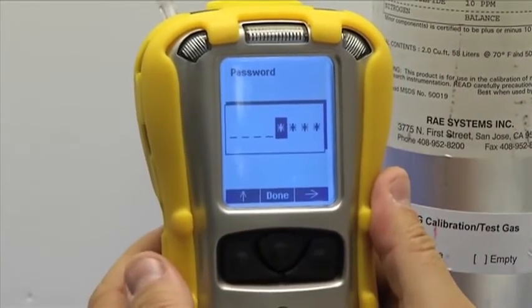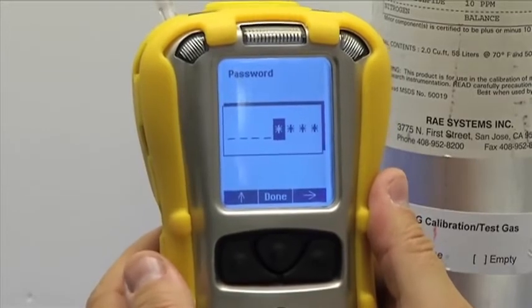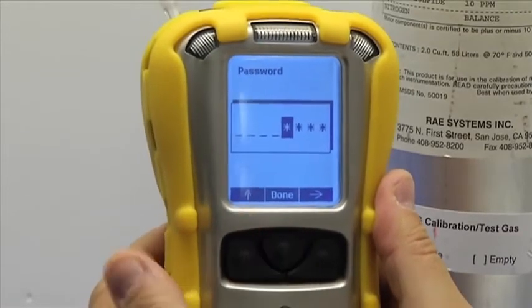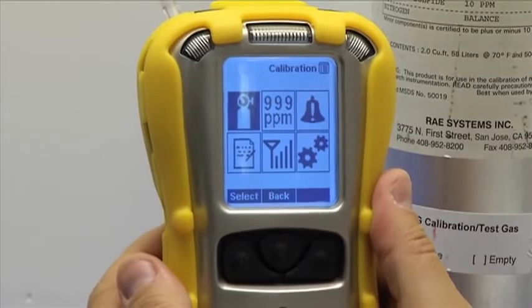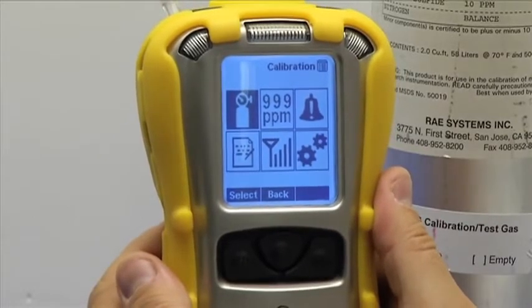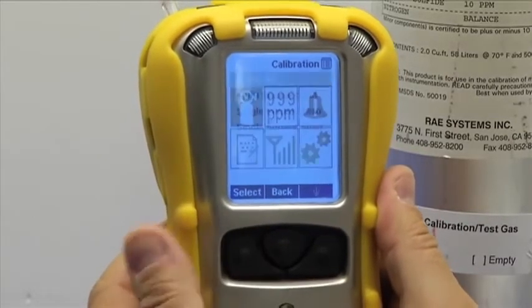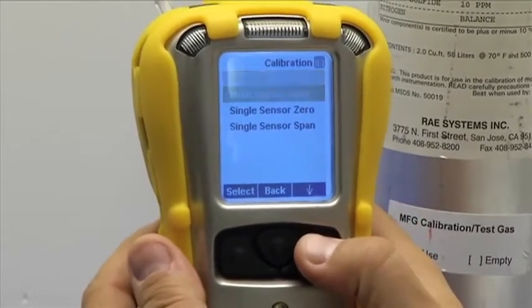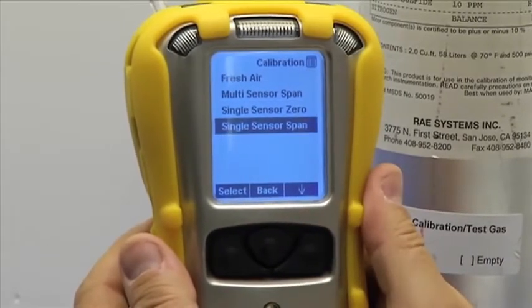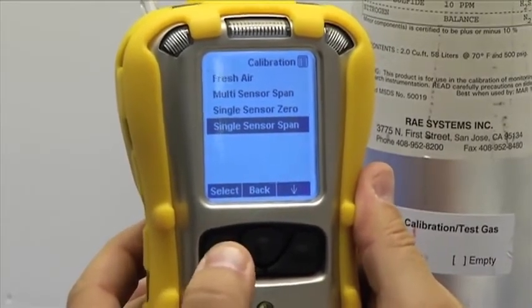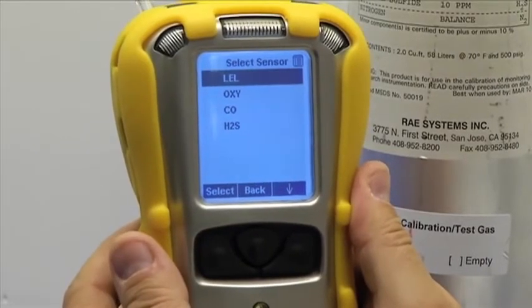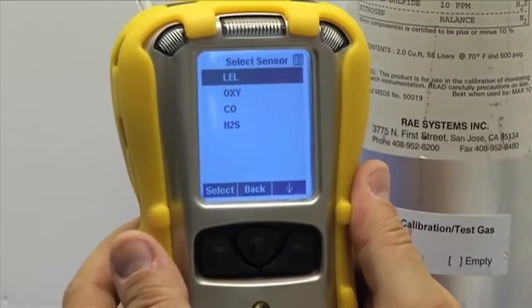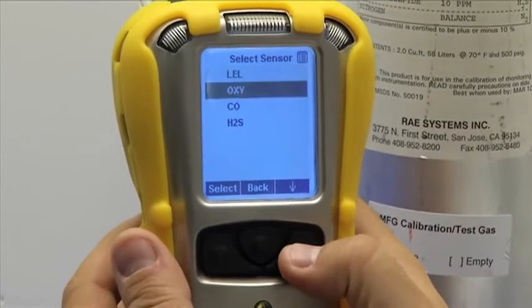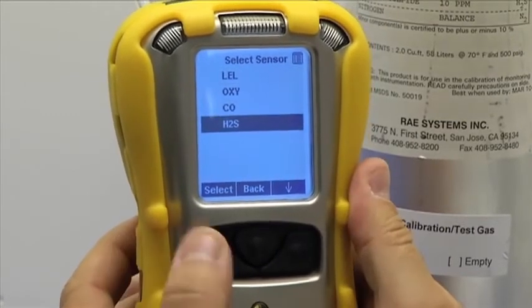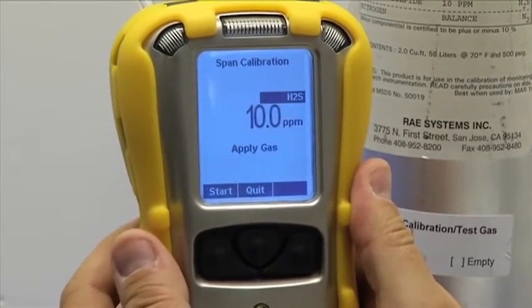Imagine a situation where I do not know the password. In that case, I would press Mode, and the instrument takes me to a limited calibration menu. I would go there and select Single Sensor Span. Then I would enter the Single Sensor Span menu and pick the H2S sensor as the sensor I want to span. I would press the Y button to confirm my selection.